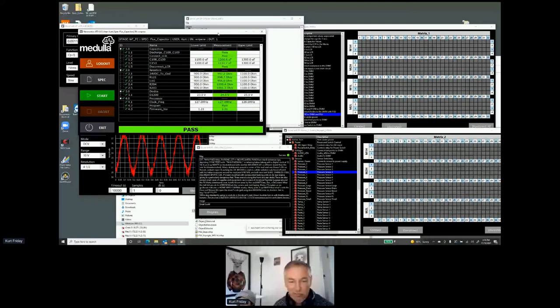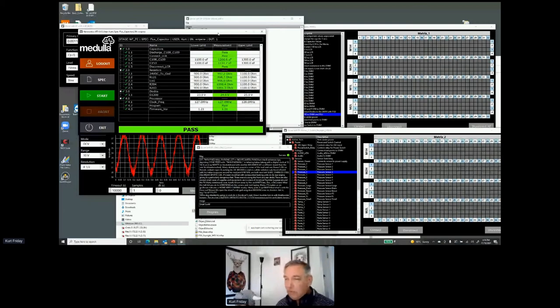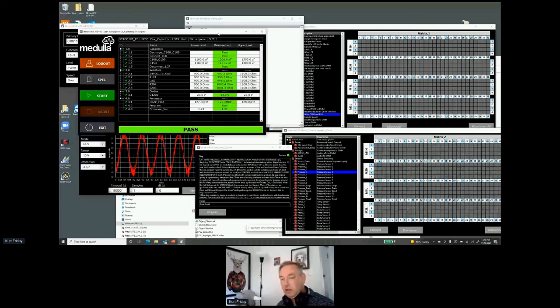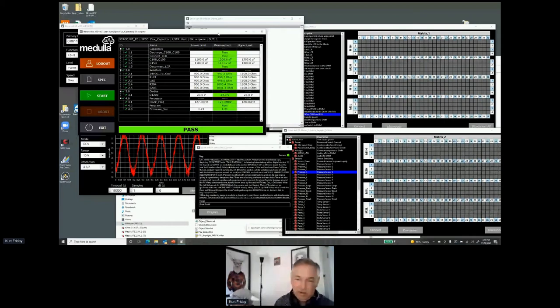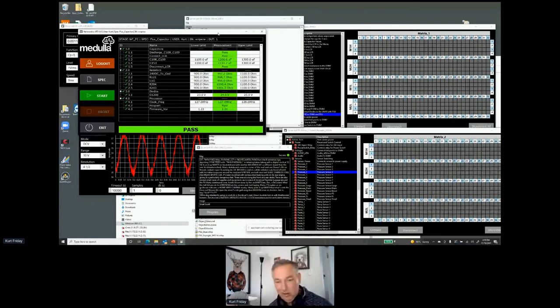You can do a lot of stuff with Viper that's not related to test systems — you can build anything out of it. We were recently working with a medical device company to build a system that would parallel-test 50 or 100 medical devices. When you plug one into a port it gets detected, spins up an engine in the background — all running on an industrial controller in RT — that engine tests that particular unit. Over that was a server managing everything, and a multi-connect server allowing tablets to connect and show the whole floor's progress, interact with individual units. Operators walking around the line with tablets, the system just executing tests.